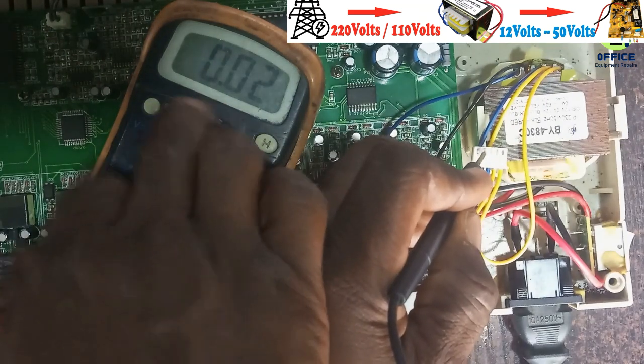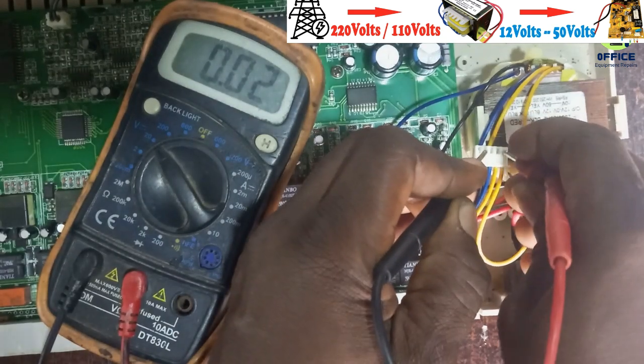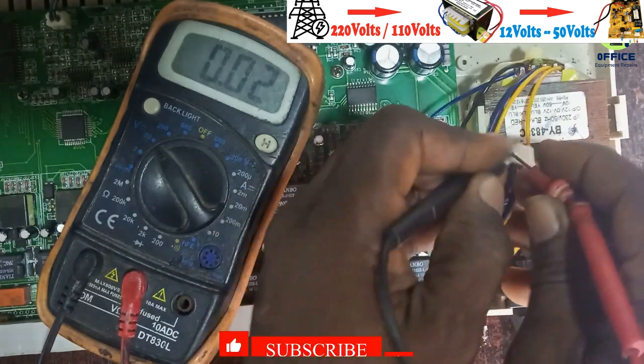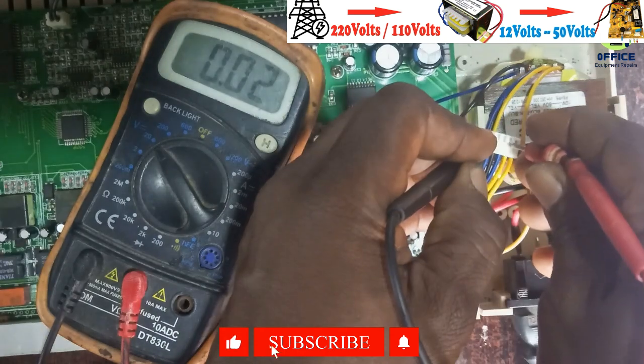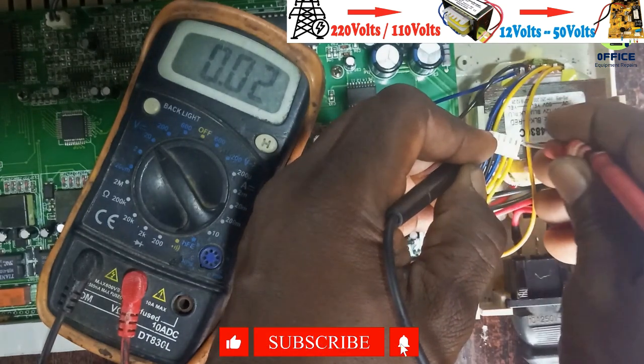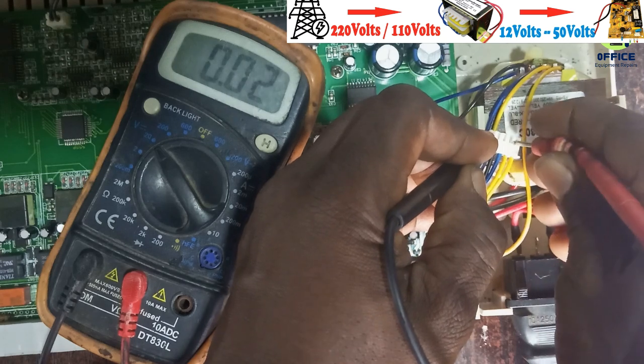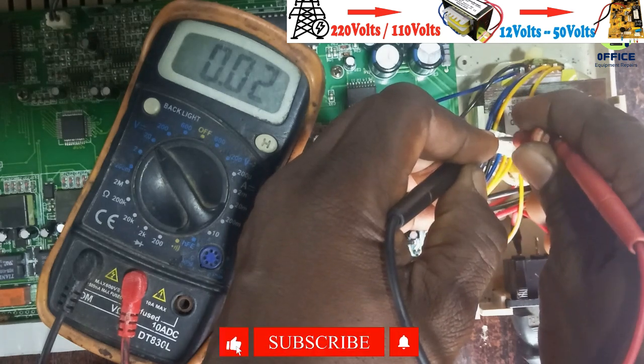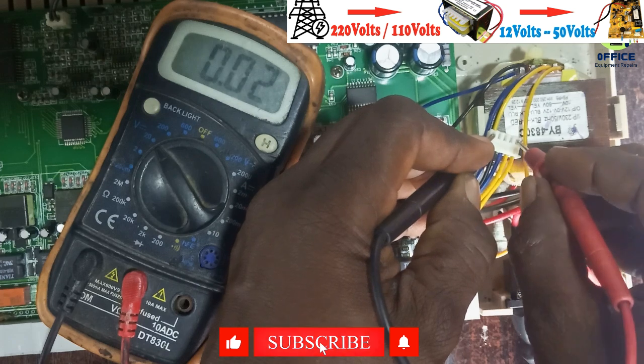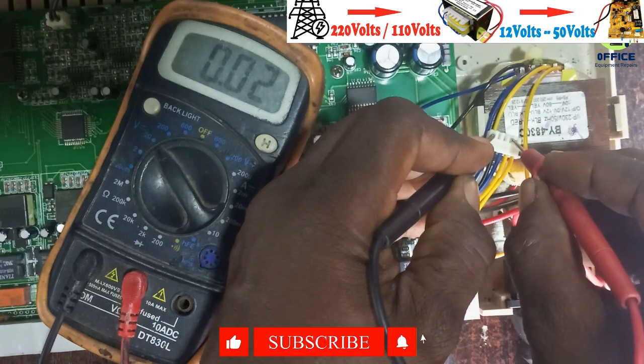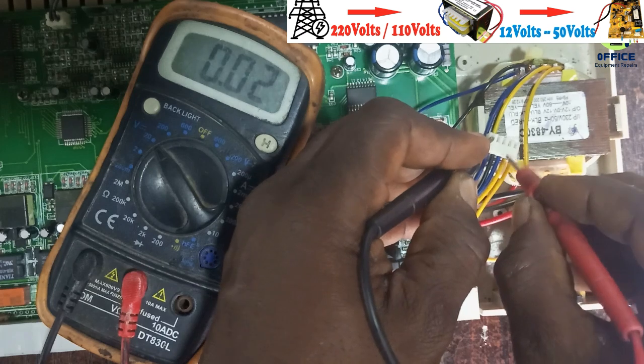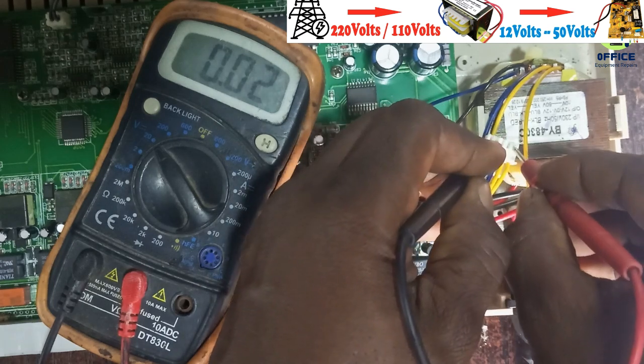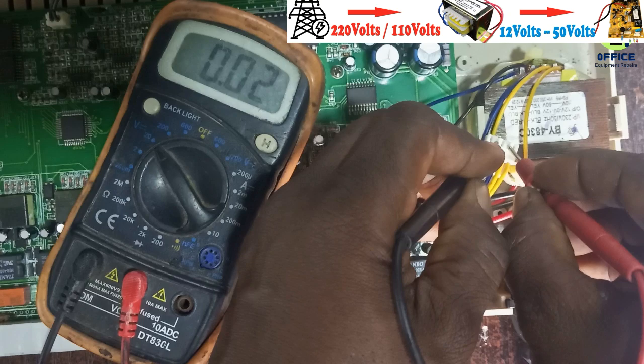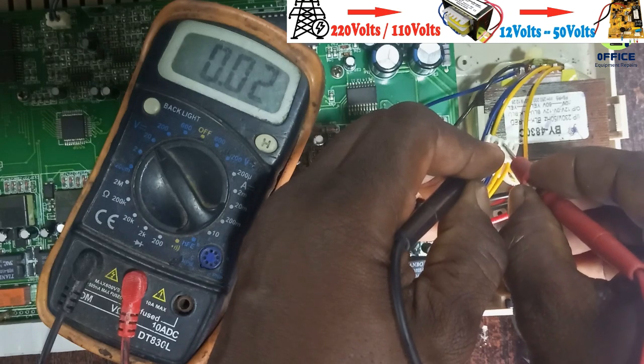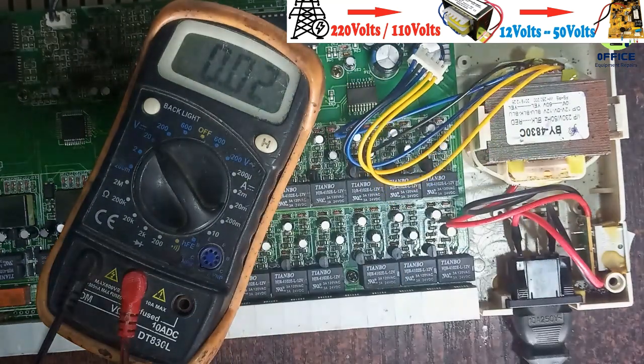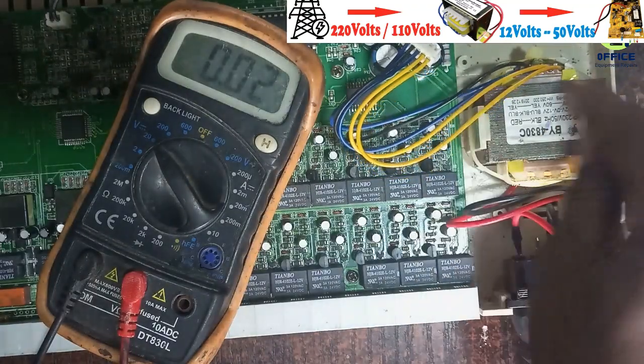You can see this 0.02. The voltage is going to remain the same, 0.02 on all of the contact points, which means there is a problem somewhere. It is not supposed to be that way. There is definitely a problem somewhere. 0.02, 0.02 here, 0.02 here, no movement at all. So something is definitely wrong with this transformer right here.